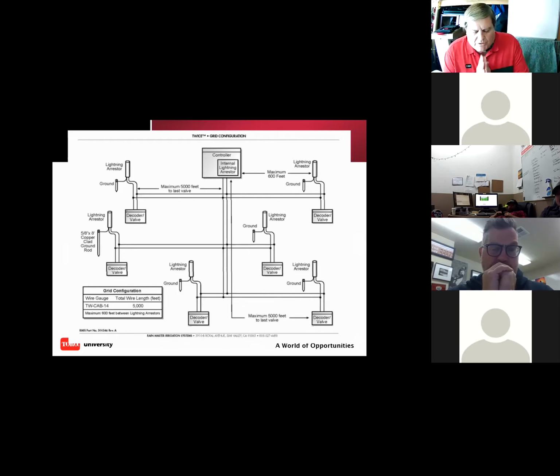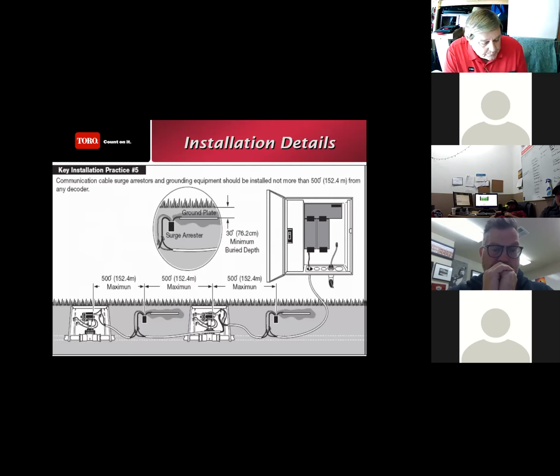All right, whether it's a loop or you go out and spread off in different directions, always, always remember to put the wire connection inside of a valve box. It's so important that you do so, so that you can find it to replace it if need be down the road. How you do the grounding of them is also brand specific. Here they show the surge arrestor. Here this one recommends a ground plate with a fill, as they call it, a moisture enhancement material around the ground plate. Either way, this one has a 500-foot maximum distance.